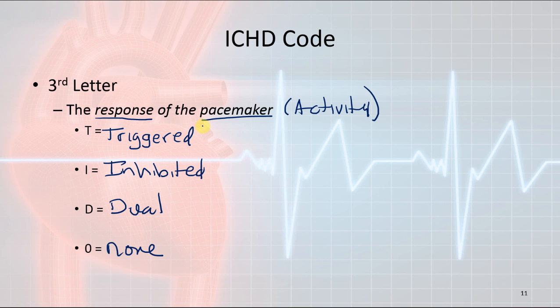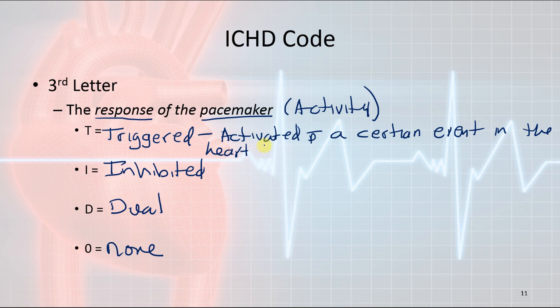What does each one of these mean? Triggered response, or the triggered activity of the pacemaker, means the pacemaker will depolarize after sensing a certain event, or the pacemaker is activated after a certain event in the heart. For example, a P wave may trigger the event. So if the pacemaker senses a P wave, the pacemaker will be activated to do something specific.